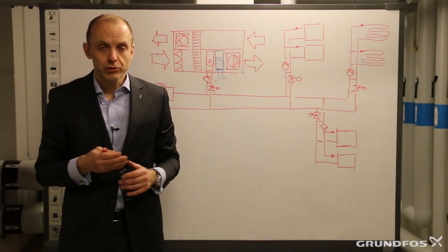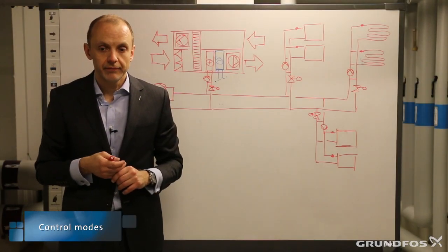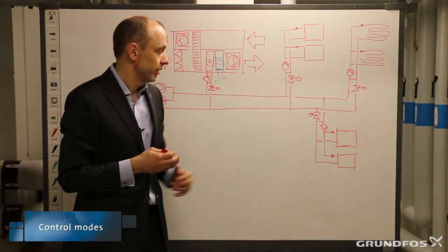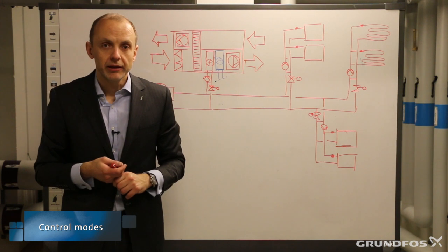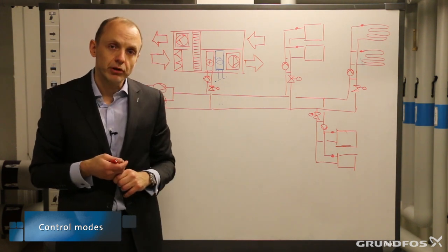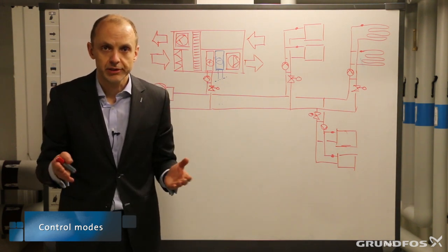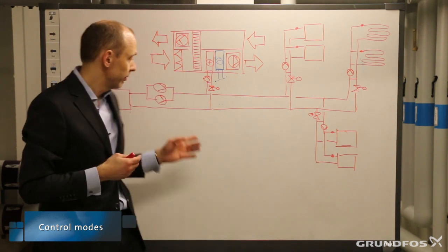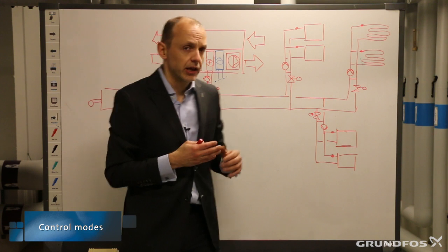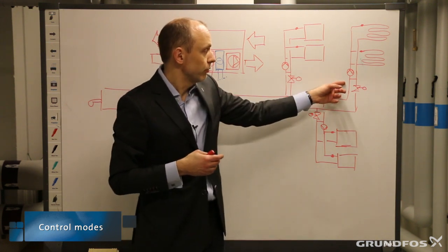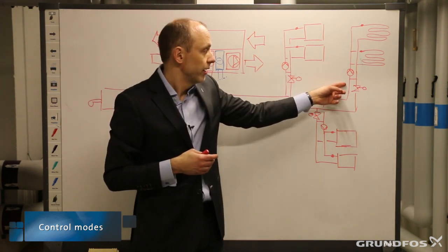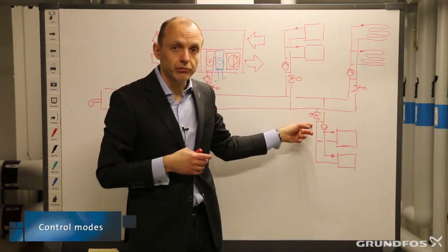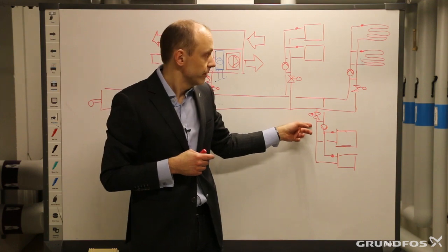So let's talk about control modes. Now we have added four mixing loops in this system, and we have the opportunity to run with different control modes. We are not dependent on the control mode of the main pumps — we can, for example, let this one run with constant pressure while these others are running with proportionate pressure.